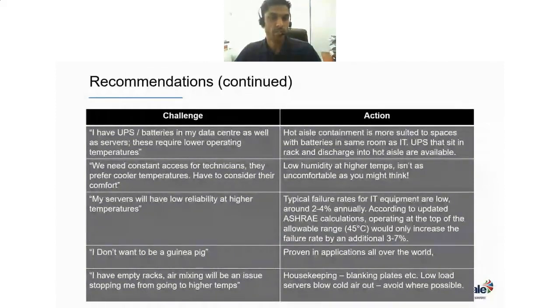Next point is my servers will have low reliability, so it's risky to keep them at a higher temperature. From the failure rate calculations, you are keeping it at 35 degrees, that's the maximum. The allowable range from the server manufacturers is 45 C. Even if you continue to run the servers at 45 degrees C, the calculation says that it's just 3 to 7%. That's the failure rate.